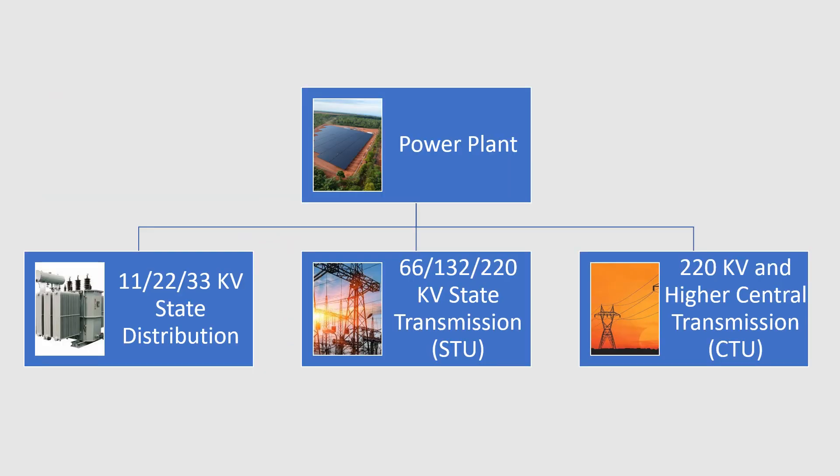If the power plant is connected to the nearest grid, that connection can be of three types. First, if the power plant is small — say one, two, five, or ten megawatts — then generally these power plants are connected to the state distribution substation grid, and the voltage level is in the range of 11 kV, 22 kV, or 33 kV.